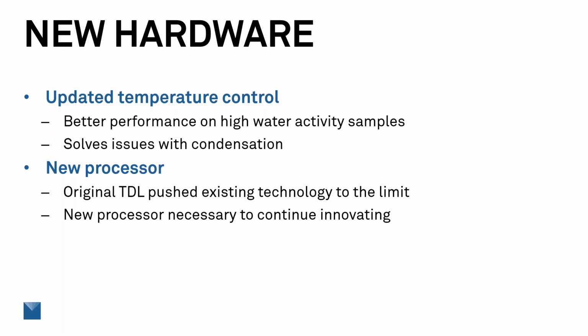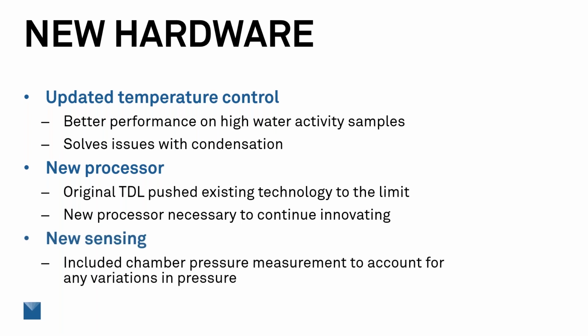And then finally, are there any upgrades to the sensing capabilities? Yeah, so as I mentioned before, the water activity measurements aren't influenced at all by volatile compounds. However, there is a phenomenon called pressure broadening that is the nature of the TDL-based technology. And so in order to incorporate that, we've always had a pressure transducer on the instrument itself. But one change that we made is actually incorporating that into the chamber itself rather than on the motherboard as it currently stands, which isn't part of the actual measurement chamber. And so that allows us to better correct for any pressure changes.